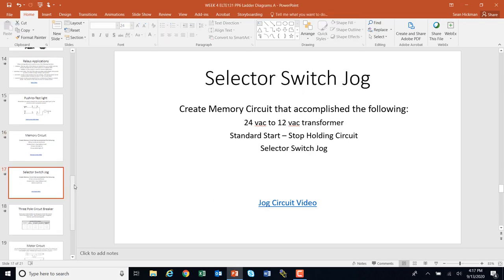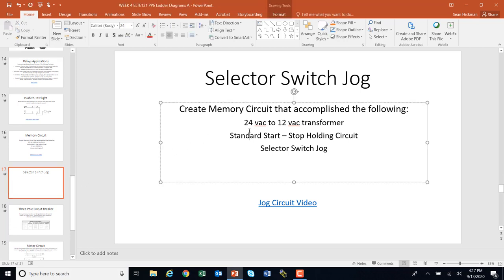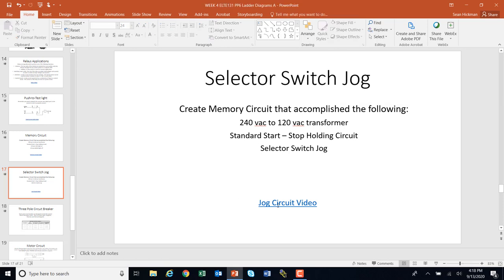We're going to do another circuit here — a selector switch jog. Again, we're going to call this 240 volts to 120 volts, so you're going to have to get good at hooking up an industrial control transformer to get a 2 to 1 ratio. You also need to know how to do the 4 to 1. This circuit will have the start-stop holding and we're going to add a selector switch, so there will be a variety of different symbols. Go ahead and stop and watch this video on the selector switch jog and how to hook it up.